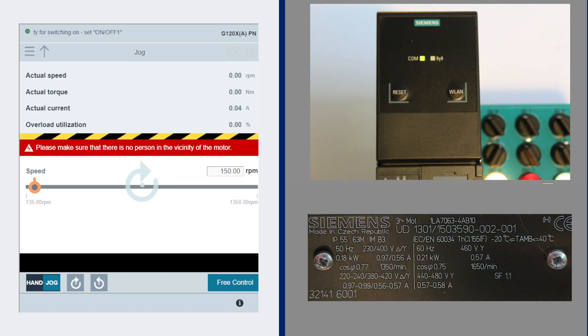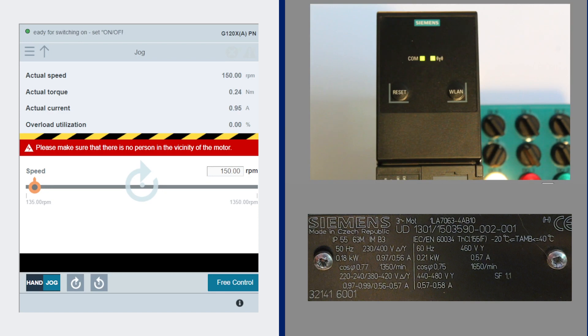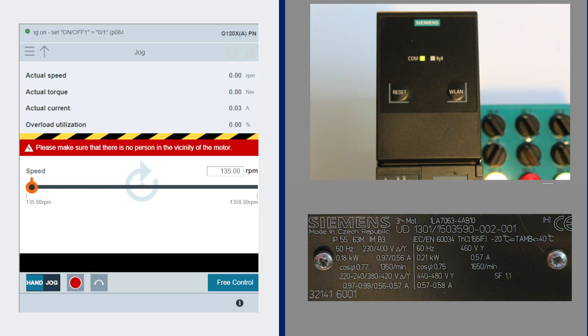You can see this is a pump or a fan drive—it won't go backwards, but it will go forward to the specified jog speed. Or you can run it in hand mode, which is not momentary. That's a maintained type of run of the motor.